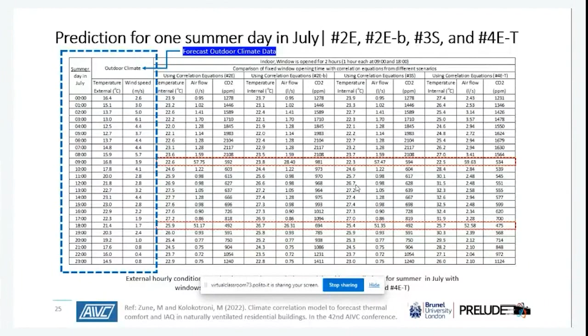This is an example of the table we use for the prediction equation. It compares how indoor air temperature, air change, and indoor CO2 concentration vary according to the different scenarios we define. It's really important to know we are using forecasted outdoor climate data in this prediction. So once we know the outdoor temperature, wind speed, or solar radiation for the next day, we just put that information into this table, and the indoor condition on the right side is predicted for us. It's a very simple calculation that can be done using an Excel spreadsheet.